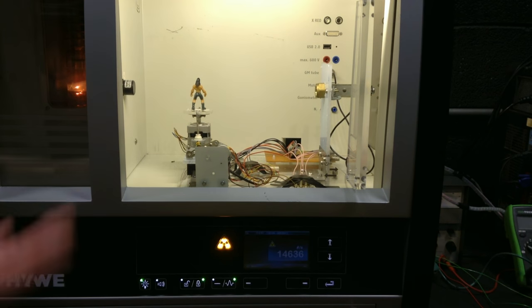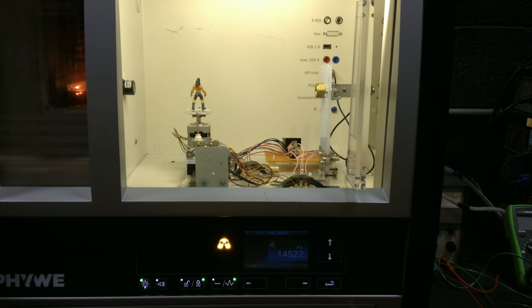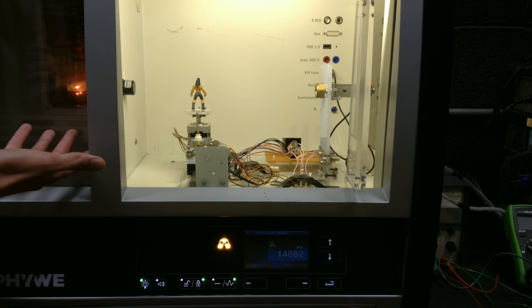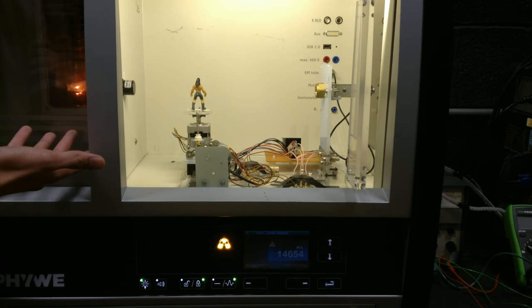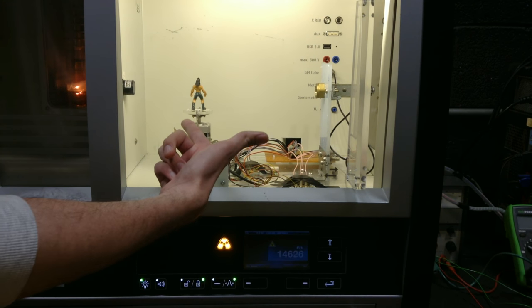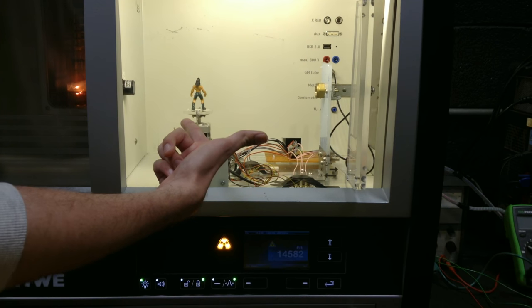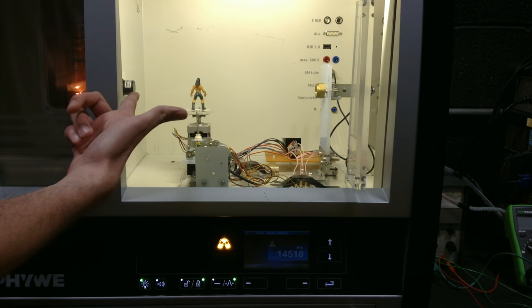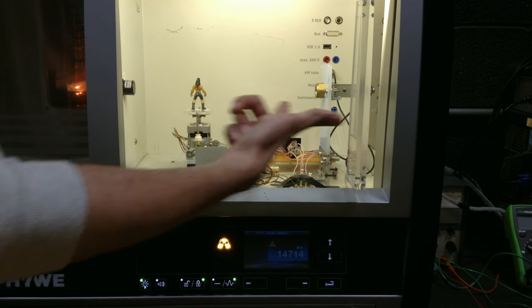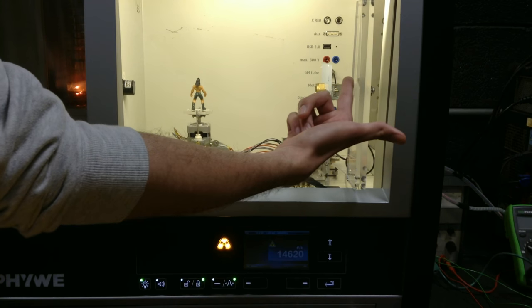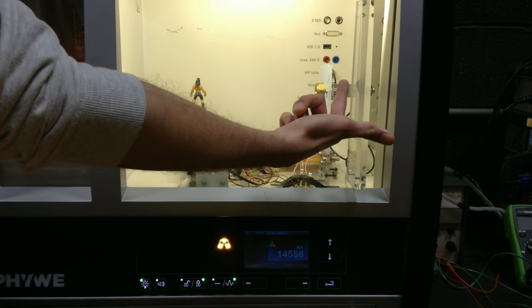So this here is the instrument built into the X-ray chamber. Here's the X-ray tube, it's a copper X-ray tube for production of the X-ray beam. In here on the left is a collimator through which the beam is produced. The X-ray beam passes through the sample over to a Geiger-Müller tube as a detector over here.